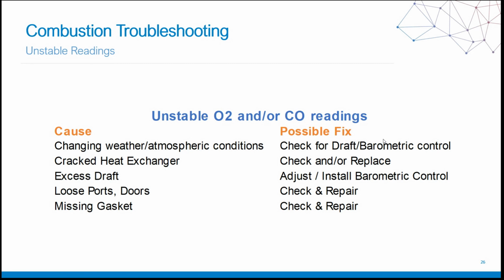When we have those changes in the atmospheric conditions inside a space, we have changes to our oxygen and carbon monoxide readings. Those things can be altered. So it's very important that we closely monitor those conditions when we talk about the actual pressure in a space. Cracked heat exchanger: obviously, the simple thing to do is to check or replace it, but it goes beyond that. We want to do our check with the analyzer, which I'm going to go over, and we also want to perform our visual inspection as well. A cracked heat exchanger can cause unstable oxygen readings and very high or unstable carbon monoxide readings.